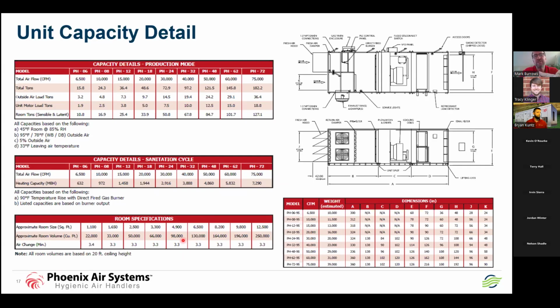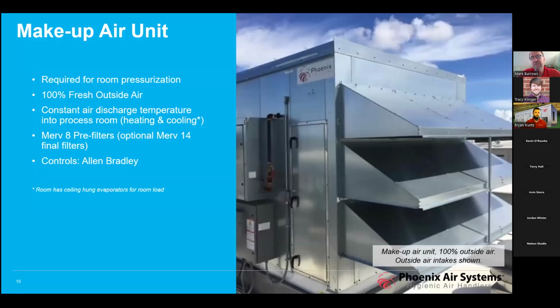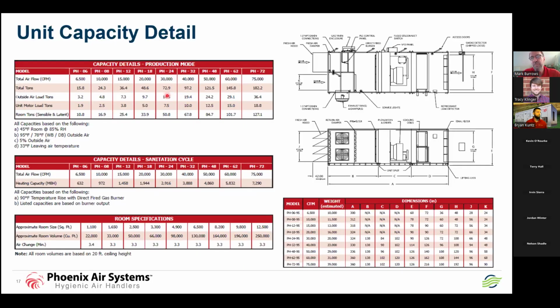The units are basically the same. We talked about the static pressure, whether it's a 3,000 CFM unit or a 100,000 CFM unit. As long as we're using the same pre-filters, cooling coils, and final filters, that static pressure is about 0.27 through the unit with another 3/4 of external static pressure. So that air is extremely predictable on and off the coils, provided the face velocities are always the same. The bigger units, anything over a 20,000 CFM unit, would be a 3-piece application. So these are going to ship in 3 module sections, which would then be bolted together at the job site.